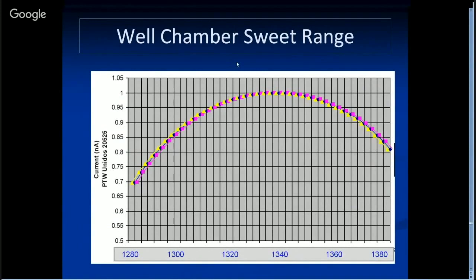You need to verify your well chamber has a sweet range - a flat response range. How do you determine that? You make many measurements with the source at different dwell positions, then find the reading maximum. That's the sweet spot for my chamber. So next time when you calibrate your source, you position it around that sweet range.